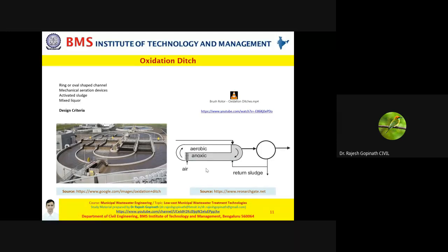Now usually when you talk about the length of the rotor, that is with respect to the aeration system, it is about 1 meter. Generally the rotor is in the form of a cylindrical cage, and the rotation, you saw the brush rotors rotating, is roughly at a rate of 75 rotations per minute. So that's a very simple depiction of design criteria for you.